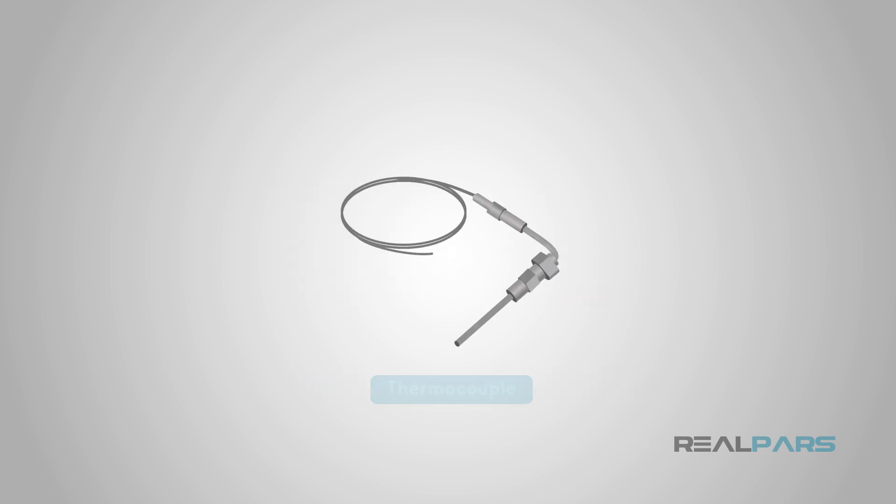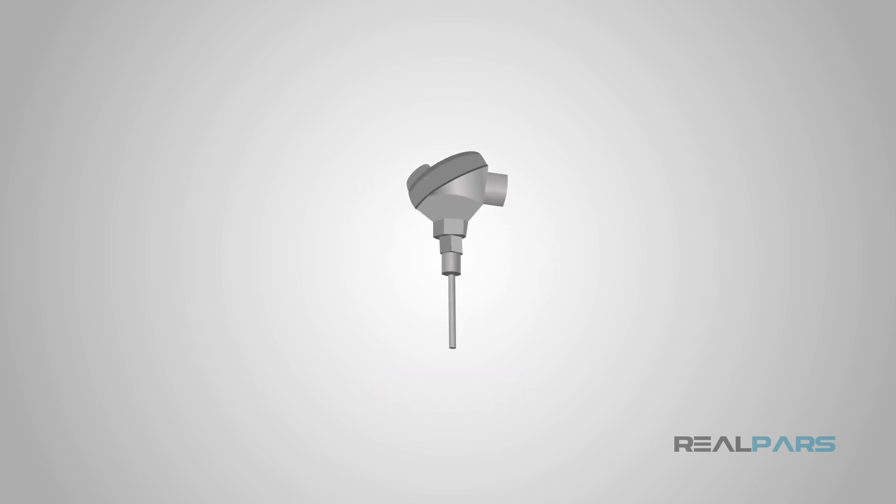There are a few general categories of signals generated by these devices. For temperature sensing, the devices themselves produce either millivolt range signals, in the case of thermocouples, or variable resistances, in the case of resistance temperature detectors, or RTDs.